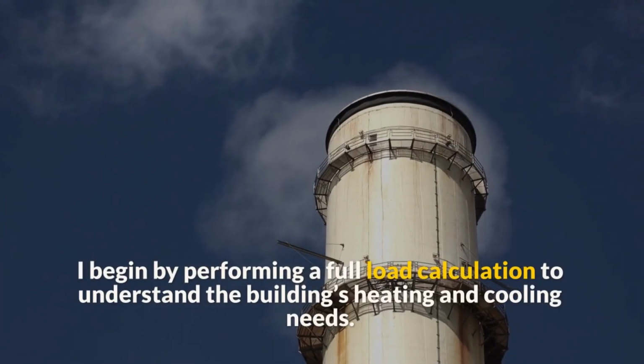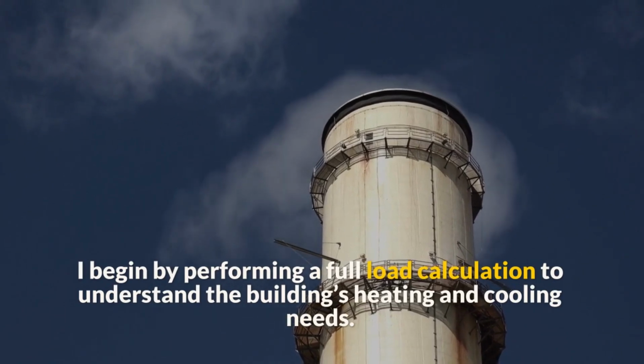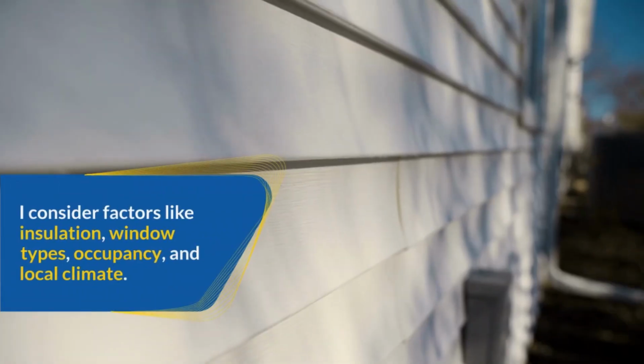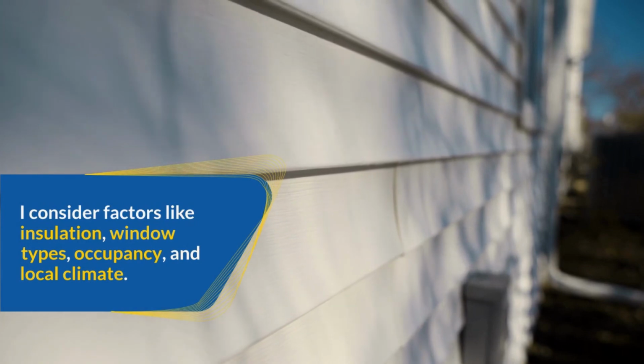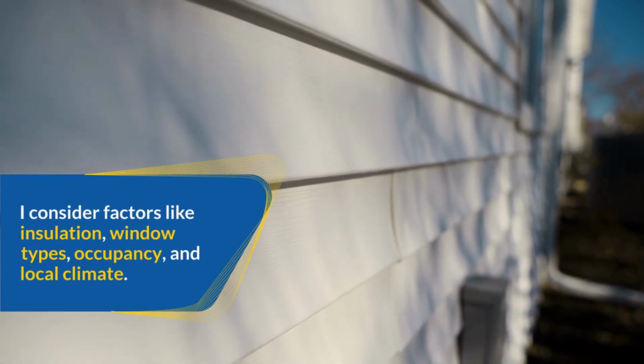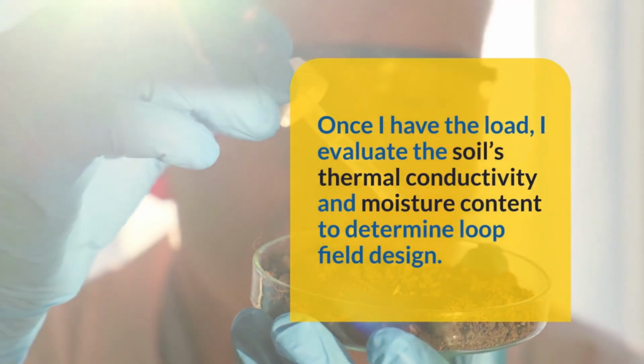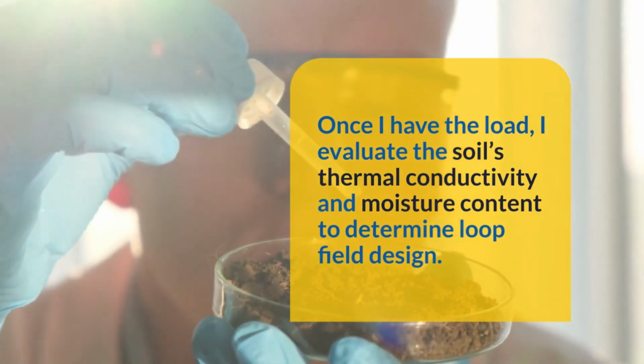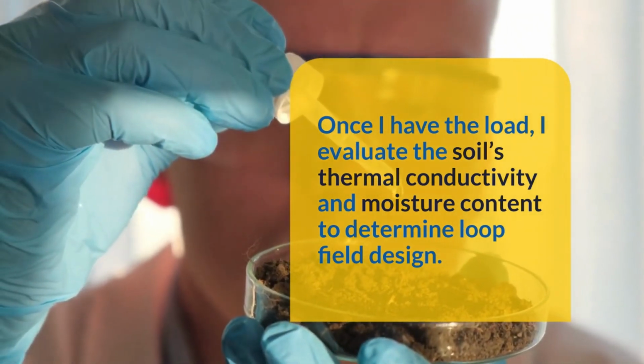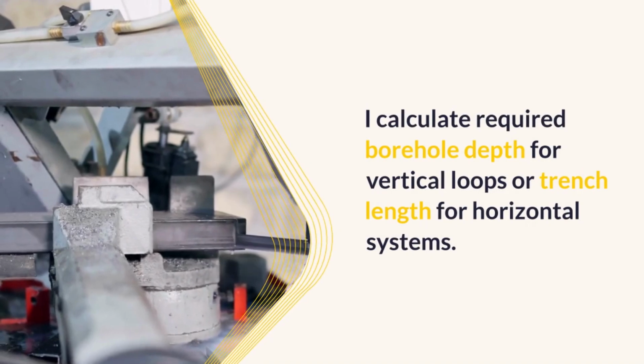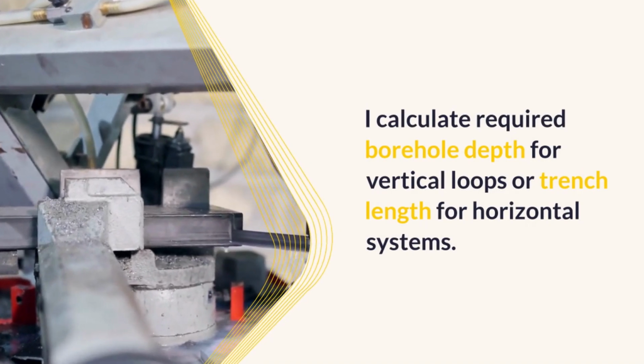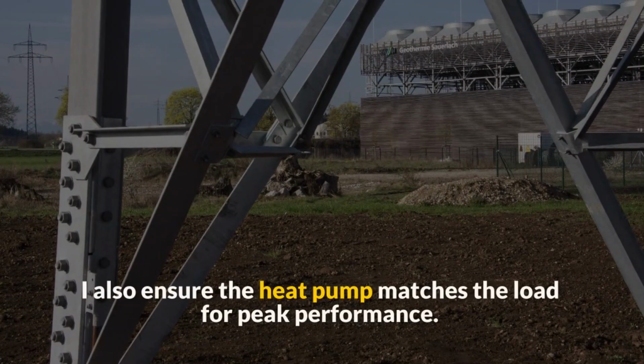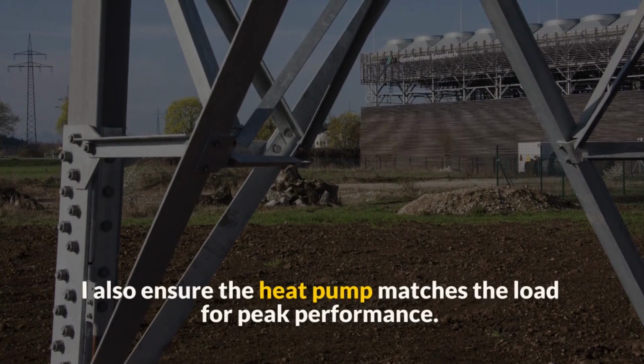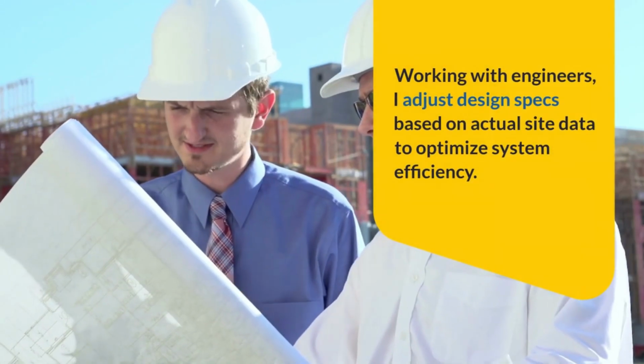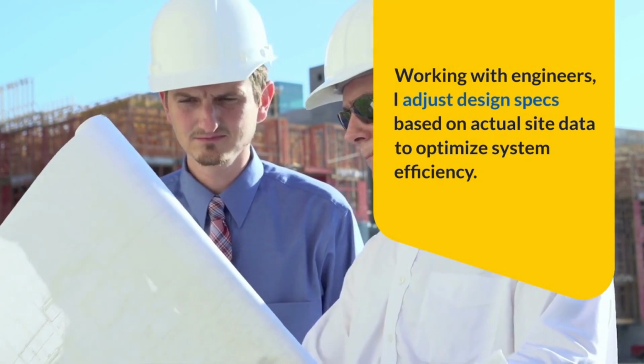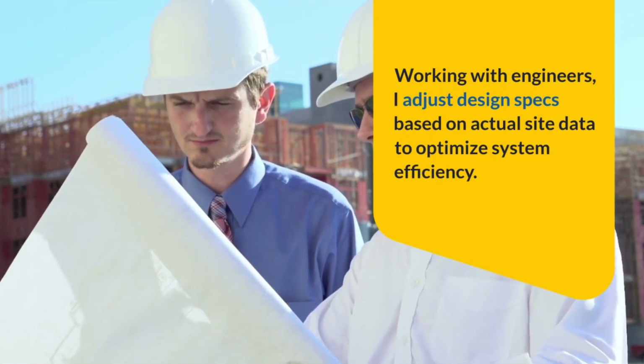I begin by performing a full load calculation to understand the building's heating and cooling needs. I consider factors like insulation, window types, occupancy, and local climate. Once I have the load, I evaluate the soil's thermal conductivity and moisture content to determine loop field design. I calculate required borehole depth for vertical loops or trench length for horizontal systems. I also ensure the heat pump matches the load for peak performance. Working with engineers, I adjust design specs based on actual site data to optimize system efficiency.